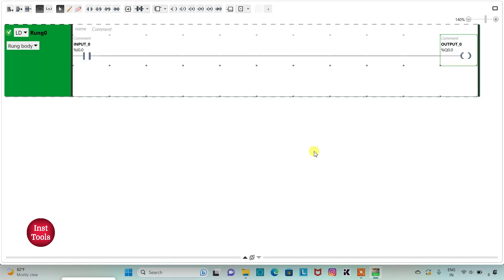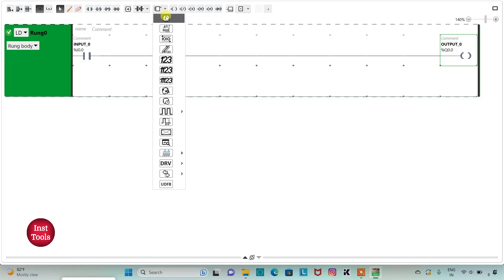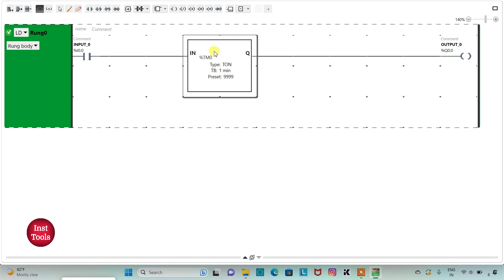So when Input 0 is on, Output 0 will be on, and when Input 0 is off, Output 0 will also be off. In the case where we want Input 0 to be on and Output 0 to remain on for a certain period of time and then automatically turn off, for this we will use a timer known as TP, that is Time Pulse. I will click on the Functional Blocks option, then select Timers, and select it here.